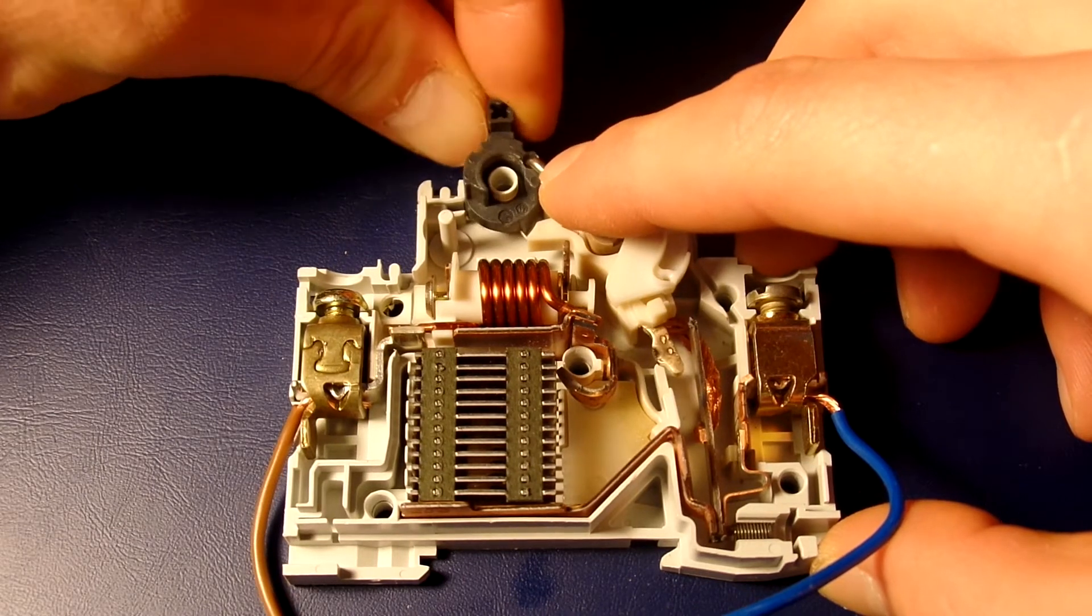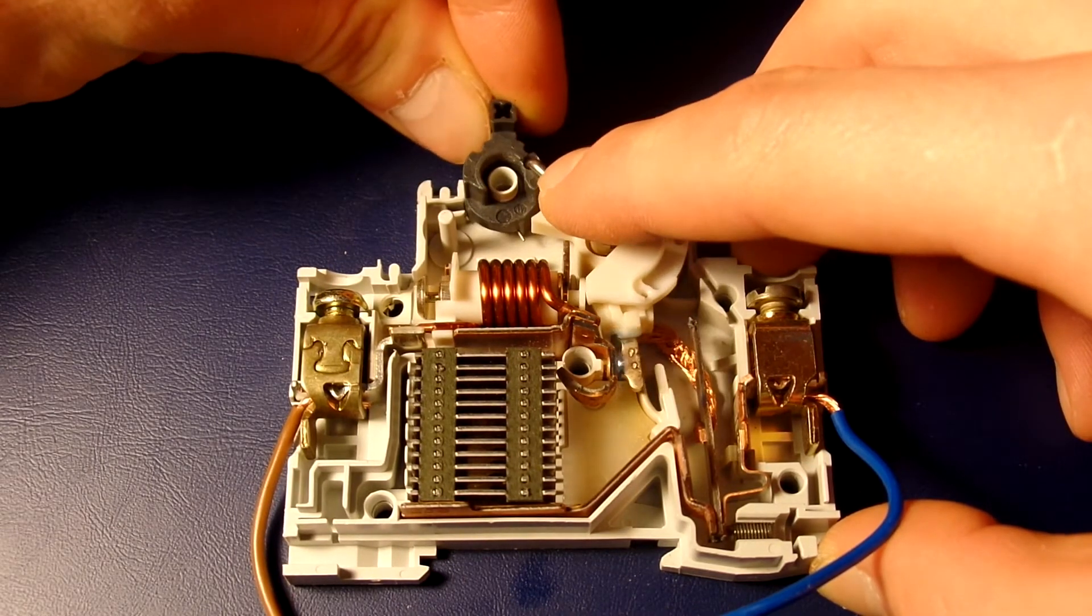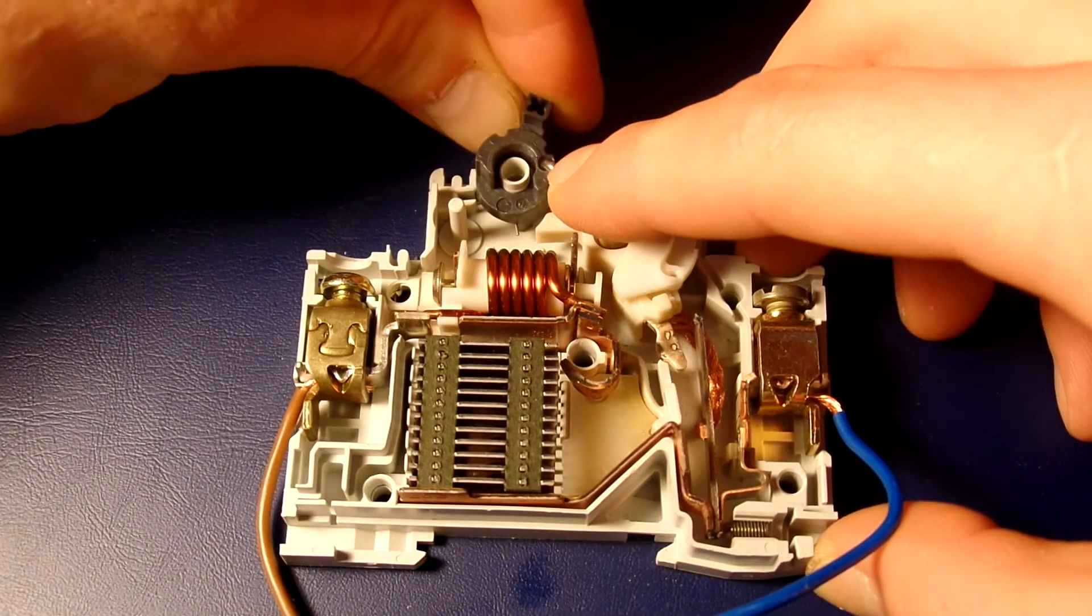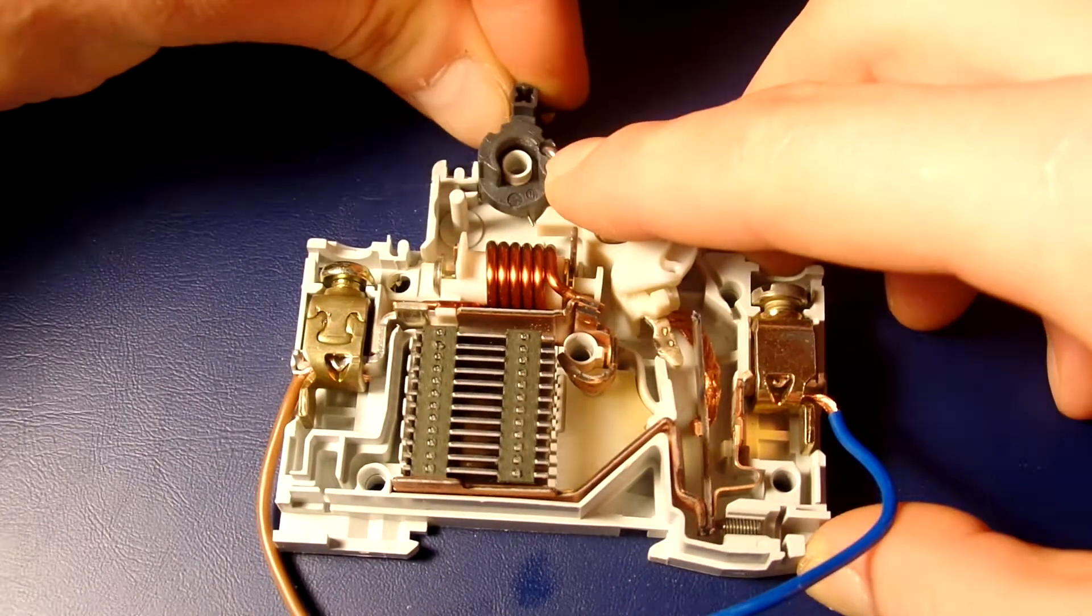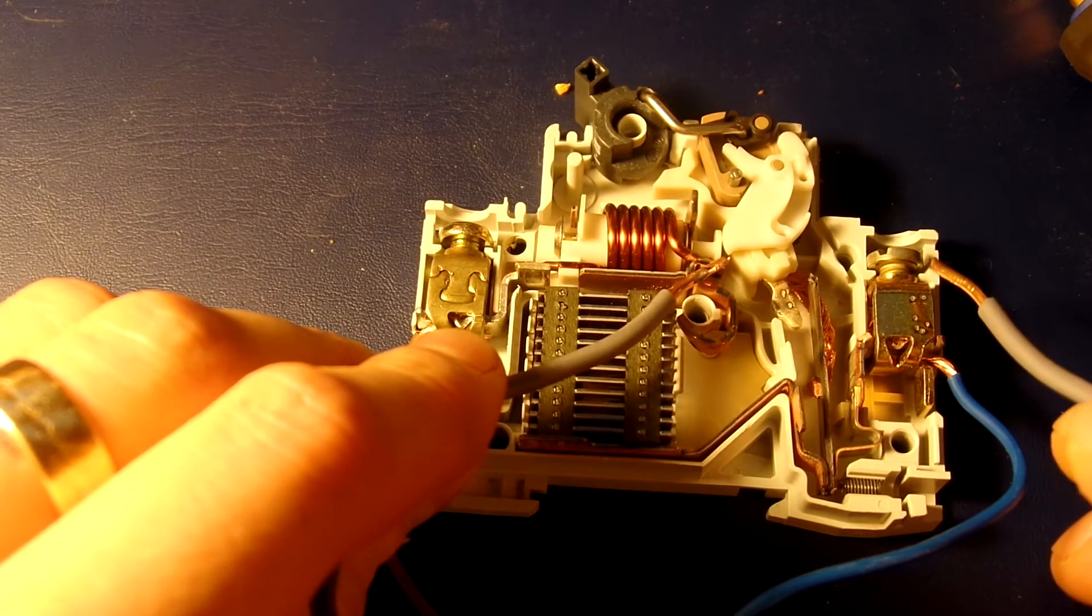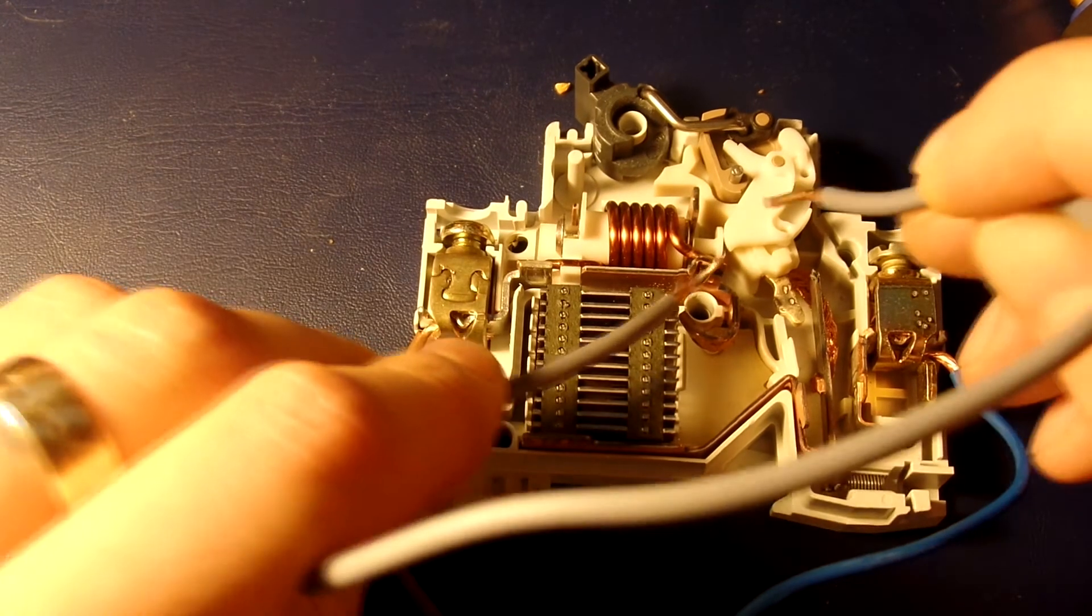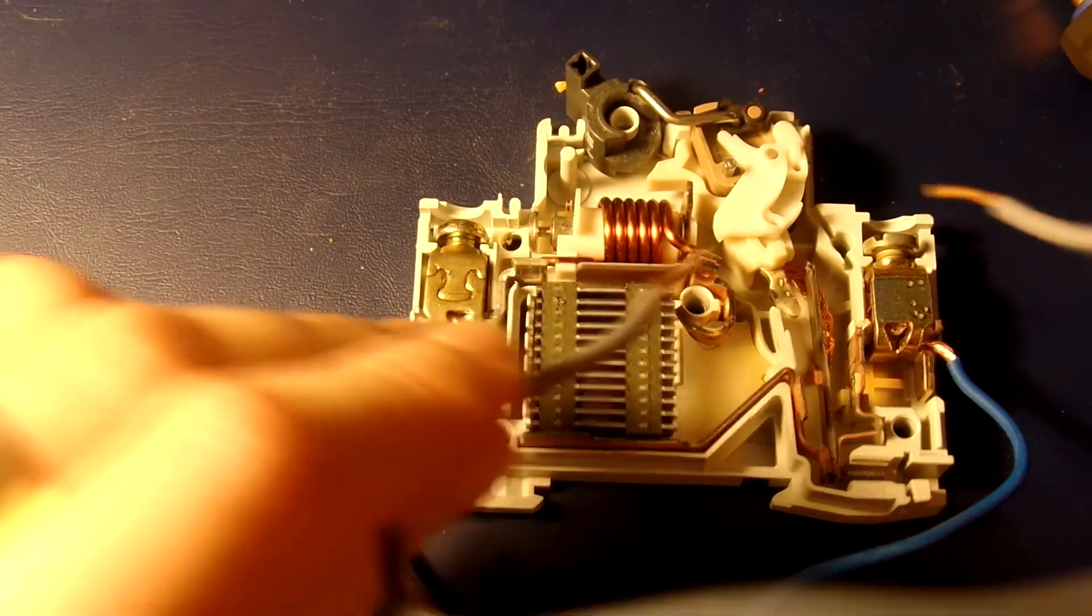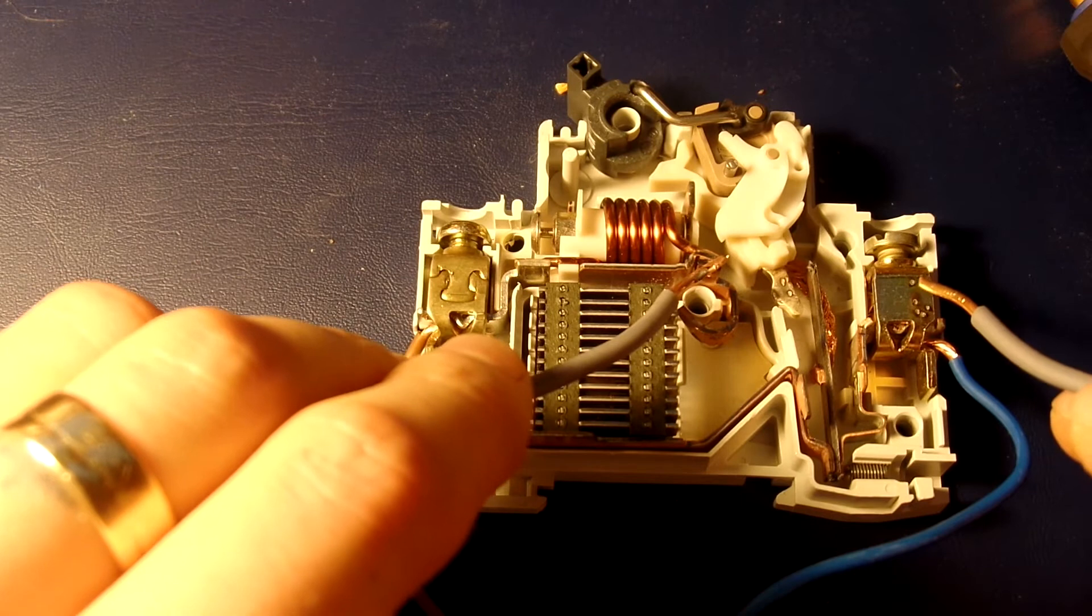The thermal portion of the circuit breaker provides an inverse time response feature which trips the circuit breaker sooner for larger overcurrents but allows smaller overloads to persist for a longer time.